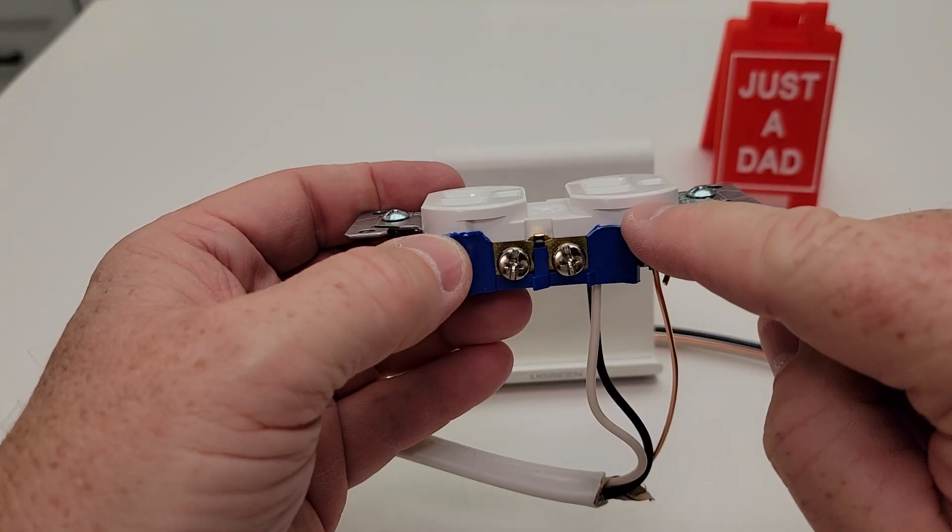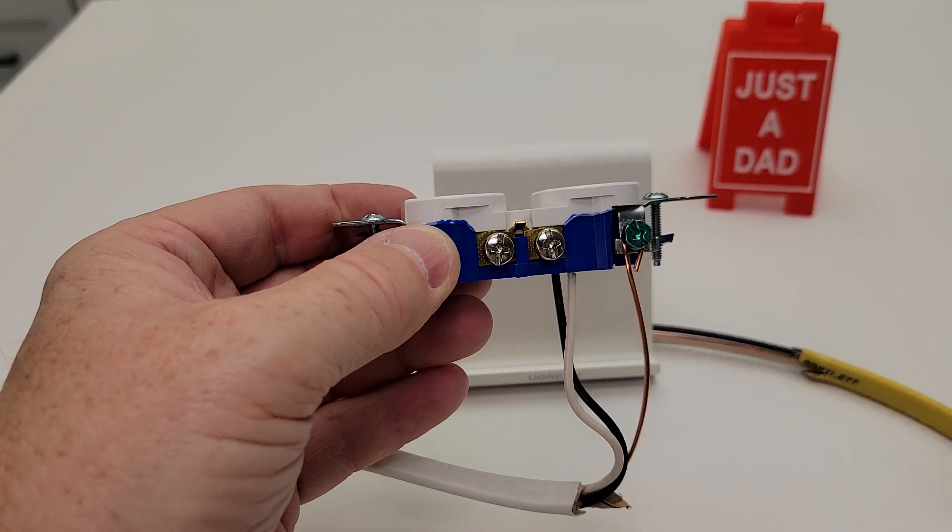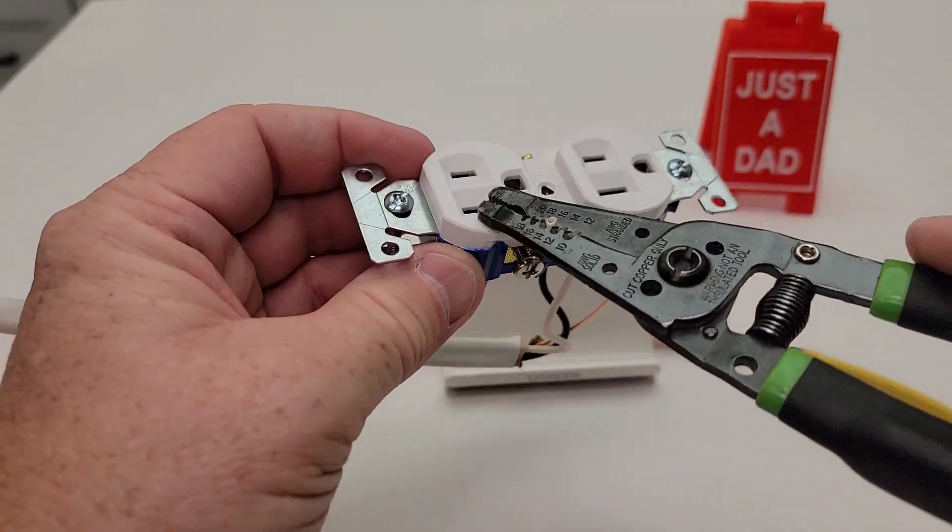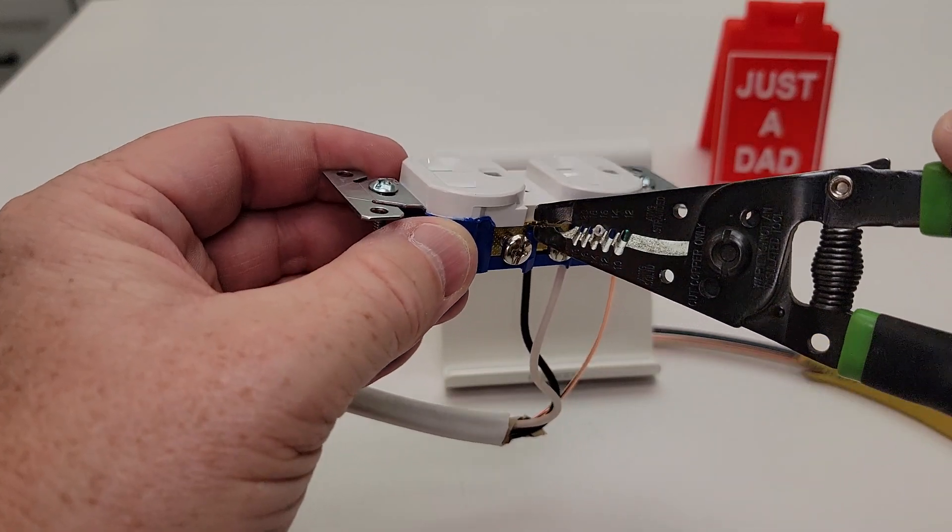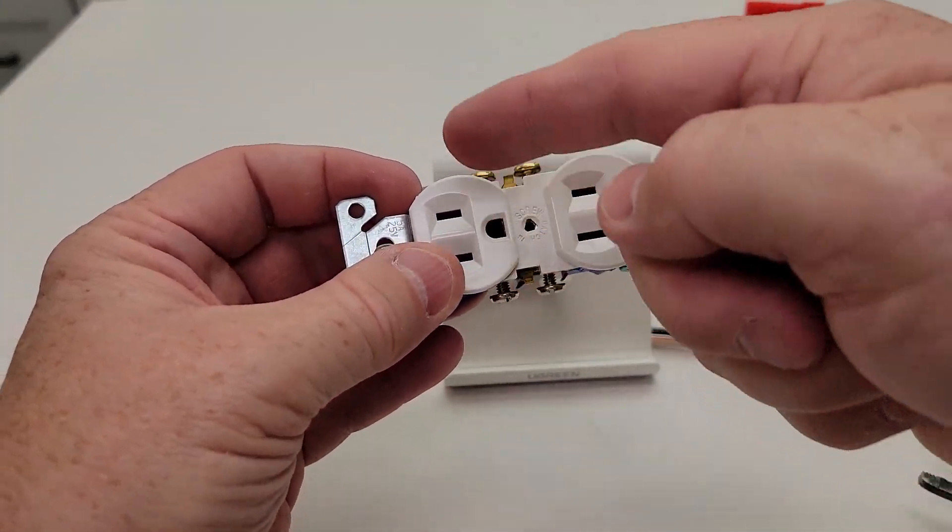Now, if I want to power this receptacle from a different power source than this one, I can break this little tab. But you're going to leave that tab installed if you want the power to be for both receptacles. But if I wanted to, I'd have to break that tab off. That separates these receptacles in half.